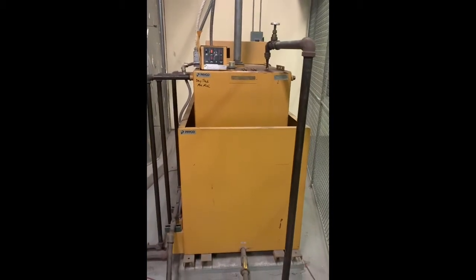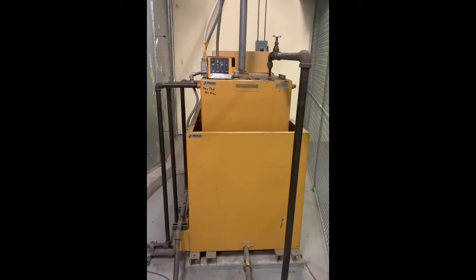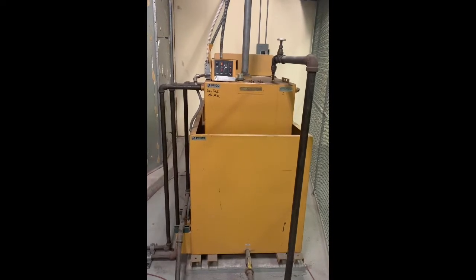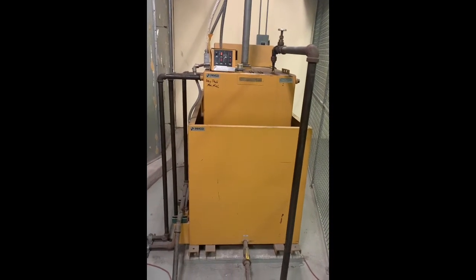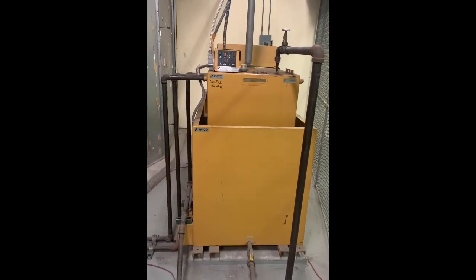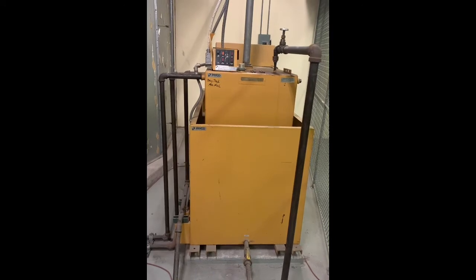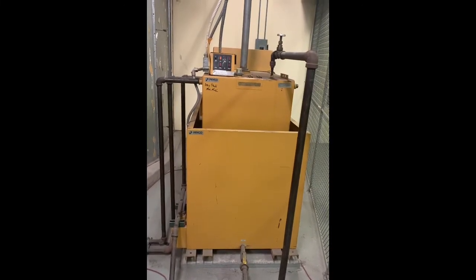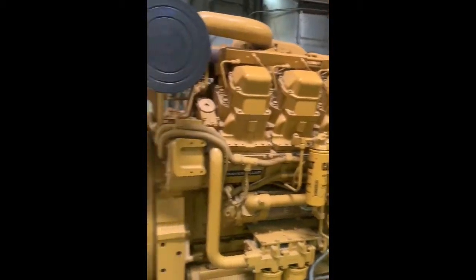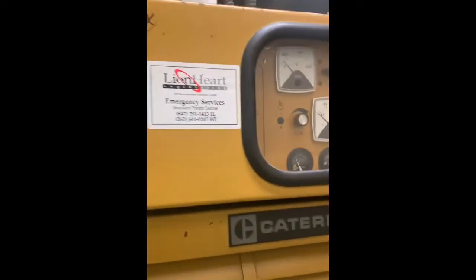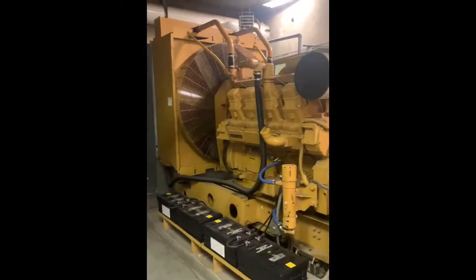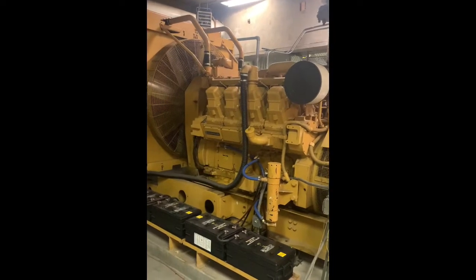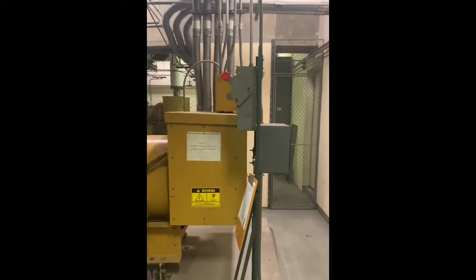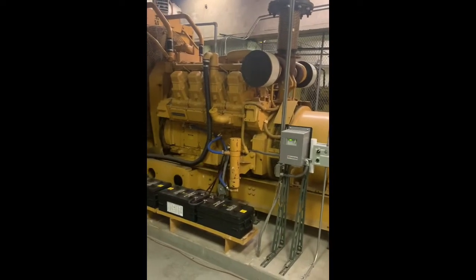It's the day tank, so there's fuel storage located under the planters out on the sidewalk on Huron Street. There's a pumping room a few floors below that will pump up to this day tank to maintain a certain amount of fuel so that this generator could run uninterrupted. We have 8 transfer switches located in this building that will send signals to this generator should there be a failure in power. We will look at those in a second.